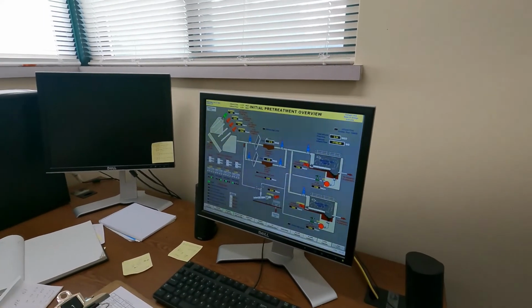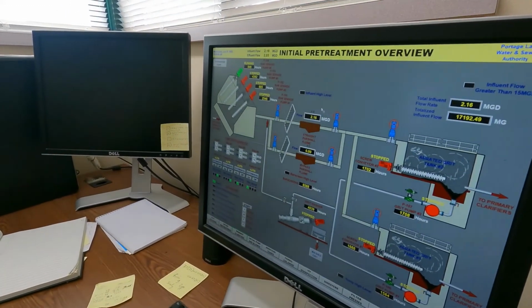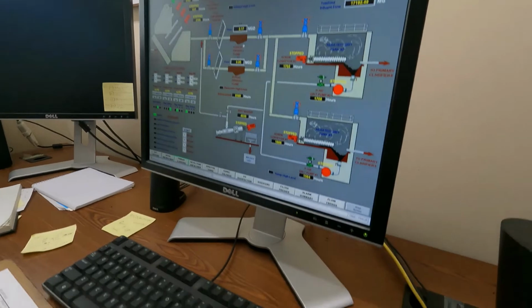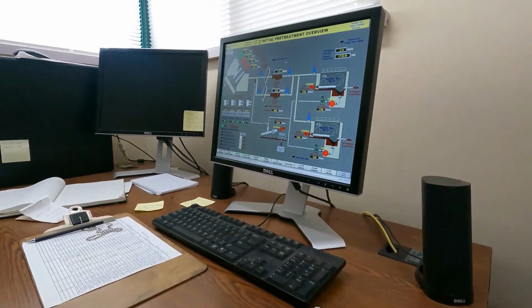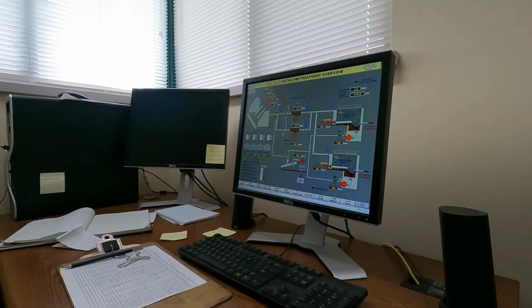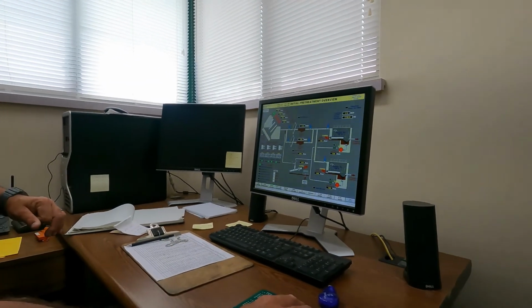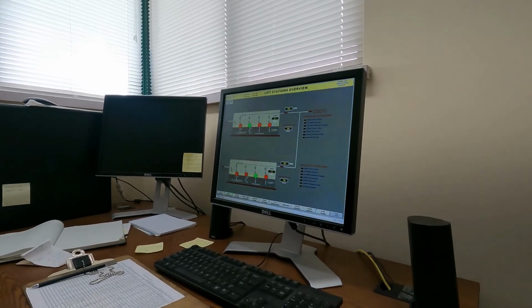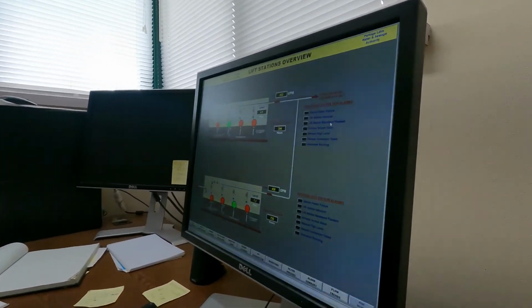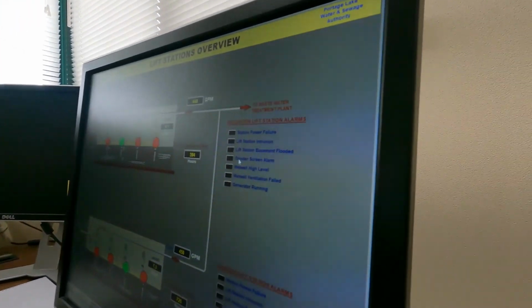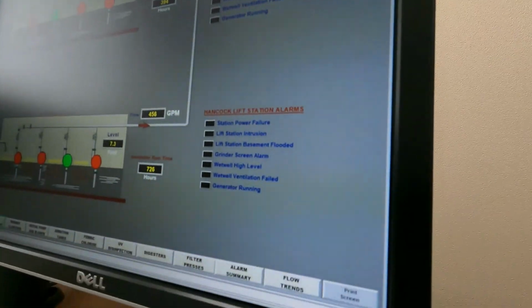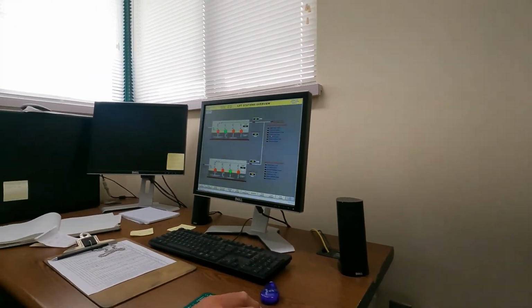So this now is our SCADA control panel. This is what's coming into the plant. It's the combined lift station flow and the gravity flow, which will come from Michigan Tech out this way, or Franklin Square. We can monitor what we just saw at the lift stations, which pumps are running. We've got a series of alarms over on the right side here for our power failure, a basement flooded alarm, which would tell us if the little sump pumps for our air release vents are working, a wet well high level, and a generator running alarm. So if we have a power failure, that'll show up out here as well.